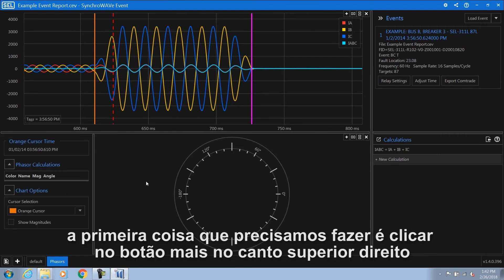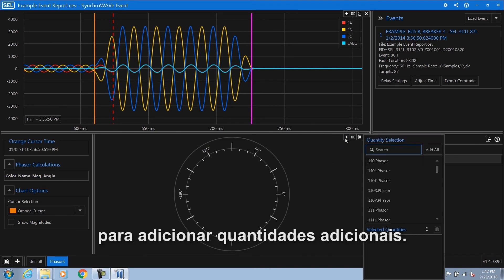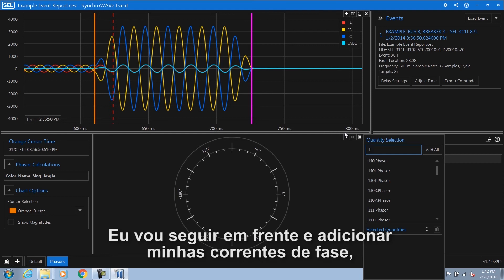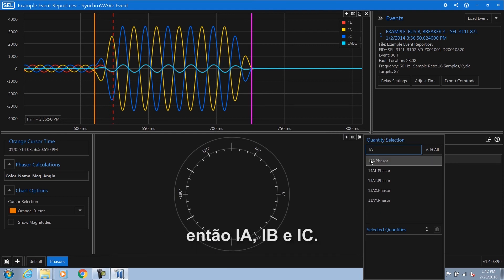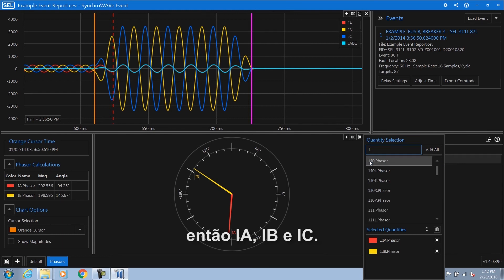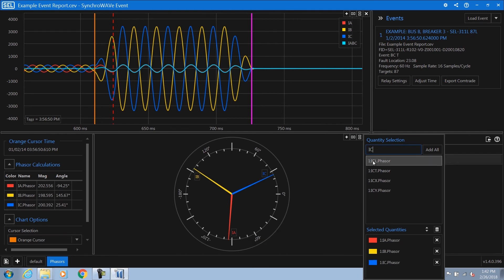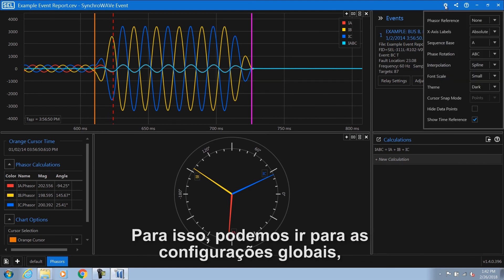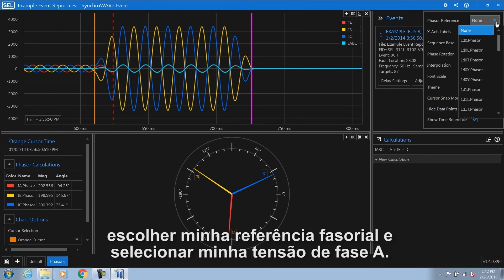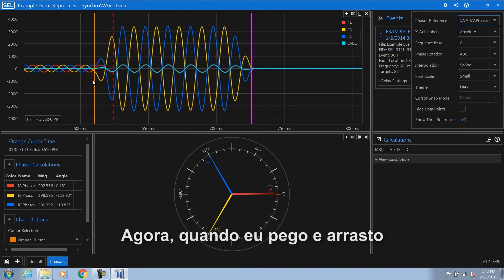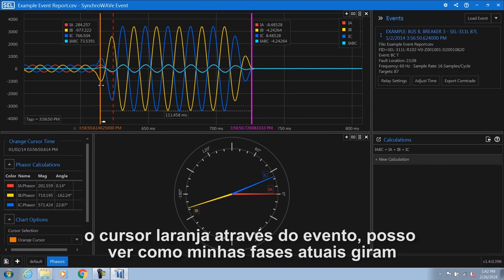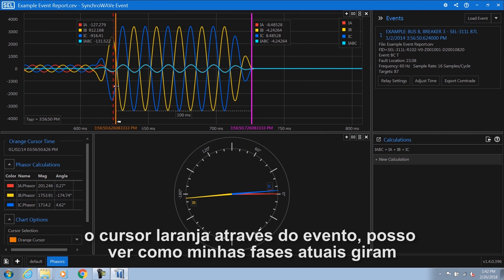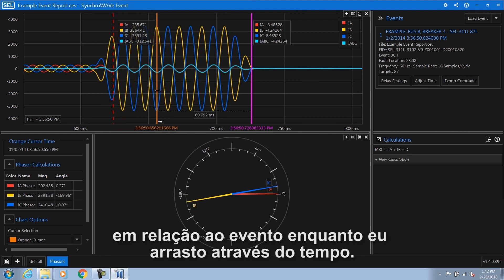We're going to select the phasor diagram for this chart. Once we've selected the phasor diagram, the first thing we need to do is click the plus button in the top right hand corner to add additional quantities. I'm going to add my phase currents: IA, IB, and IC. The next thing we need to do is set a phasor rotation. We can go to the global settings, choose my phasor reference, and select my A phase voltage. Now as I grab and drag the orange cursor through the event, I can see how my current phases rotate with respect to the event as I drag through time.